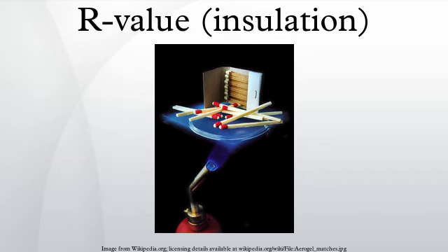Infiltration, correct attention to air sealing measures and consideration of vapor transfer mechanisms are important for the optimal function of bulk insulators. Air infiltration can allow convective heat transfer or condensation formation, both of which may degrade the performance of an insulation. One of the primary values of spray foam insulation is its ability to create an airtight seal directly against the substrate to reduce the undesirable effects of air leakage.